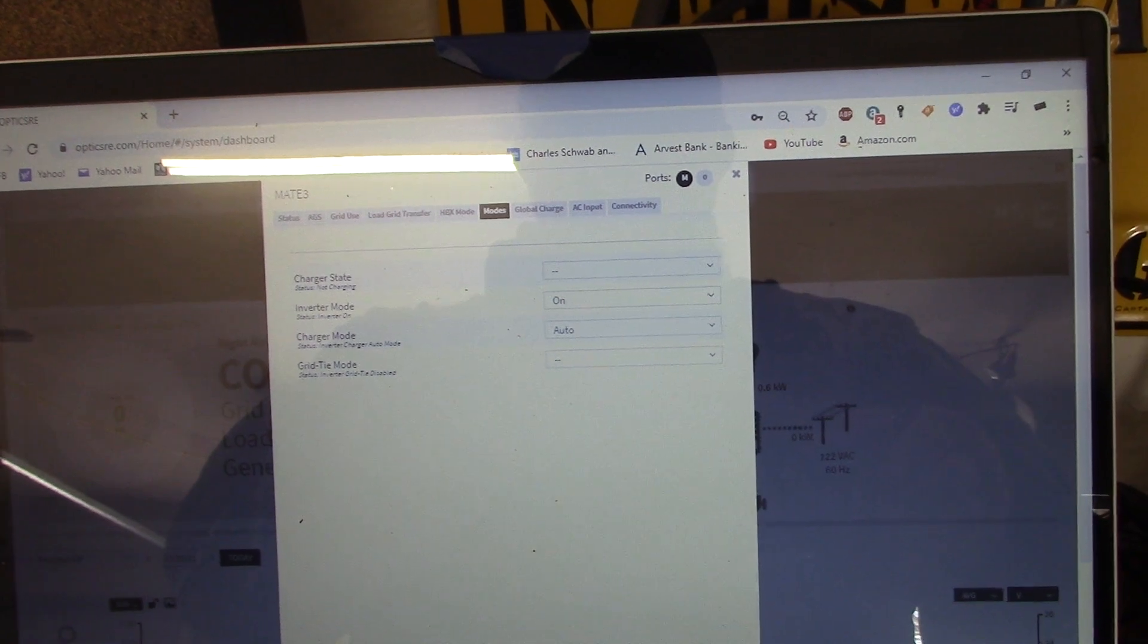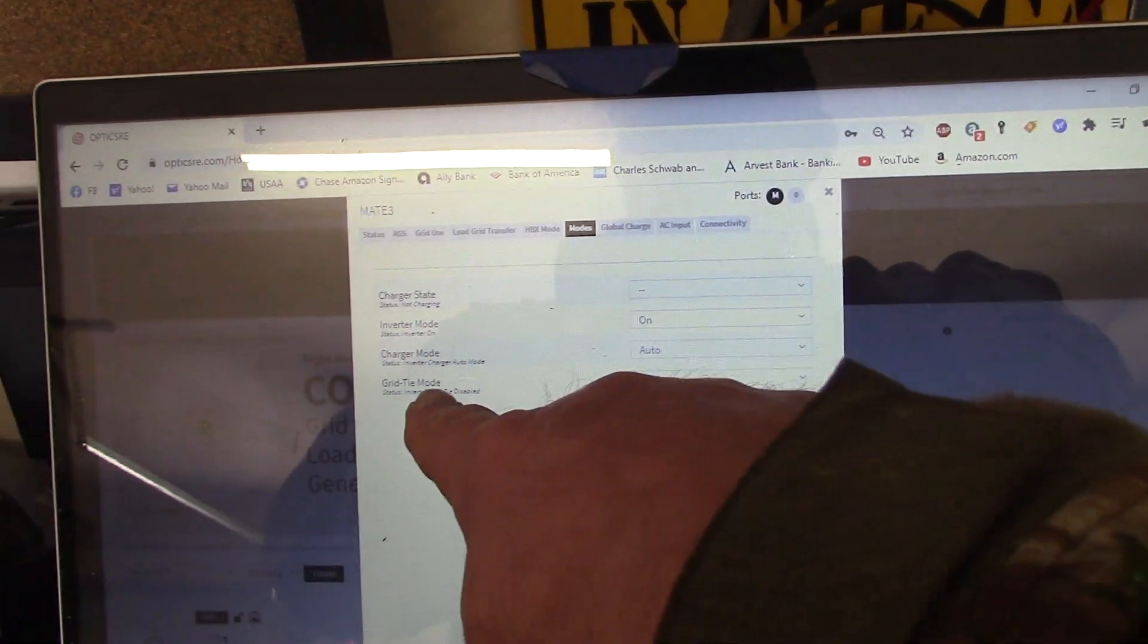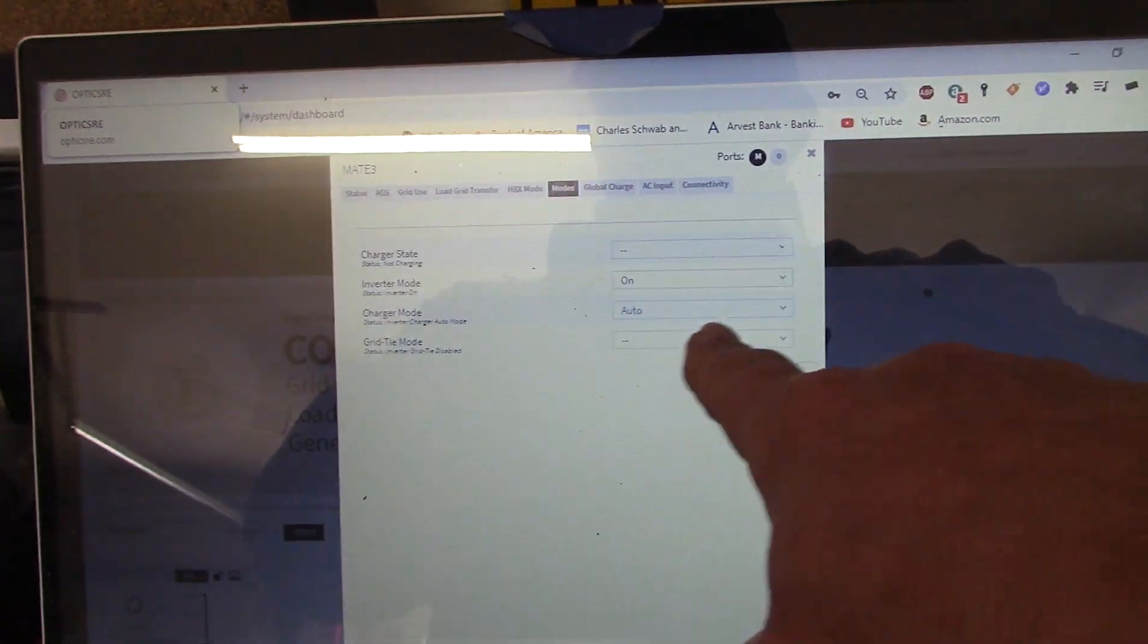And they weren't talking to each other. It was kind of manually you had to go and put it in drop AC and charge. Then automatically go back to inverting when it hits full charge. But I wanted to do it automatically. And this is where I screwed up. The charger mode on the Mate 3 has to be in auto mode.